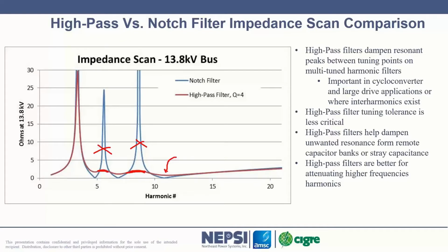But another thing that's interesting to note is at the tuning points, we lose our filtering with a high pass filter. So you give up your high impedance point between your tuning points, but at the same time, you're giving up your filtering at points here, and here. So this is where the art comes into play. How much dampening do I need, and how much filtering can I forego at the tuning points? This is the art of doing a harmonic analysis. Is you have to sometimes do an iterative process. You try to avoid notch high pass filters when you can because there's cost associated with it.